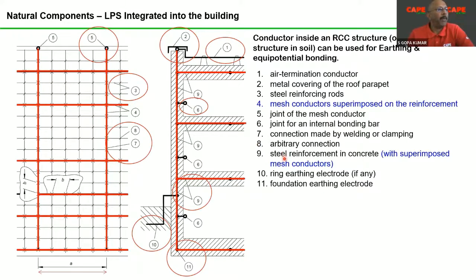Item number 9 is steel reinforcement in concrete with a superimposed mesh conductor. For high-rise buildings and buildings of larger size, separation distance is very difficult to calculate and maintain. Calculation is possible, but maintenance is practically impossible. The best method is to use the naturally available steel as a part of the lightning protection system. For example, in an RCC building, you can put an additional conductor embedded, superimposed in the reinforcement, and this conductor will support your structural steel in making the whole building perform as a lightning conductor.